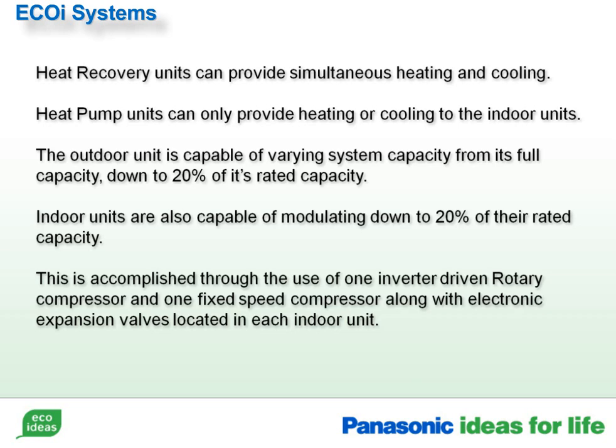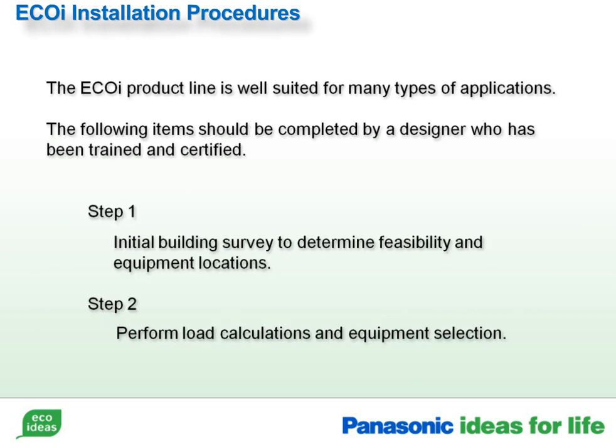The outdoor unit is capable of varying system capacity from its full capacity down to 20% of its rated capacity. Indoor units are also capable of modulating down to 20% of their rated capacity. This is accomplished through the use of one inverter-driven rotary compressor and one fixed-speed compressor, along with electronic expansion valves located in each indoor unit. ECOi heat pump and heat recovery systems are applied products. They are well suited for many types of applications.